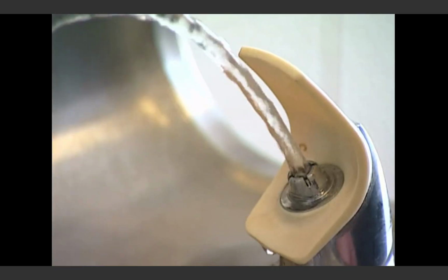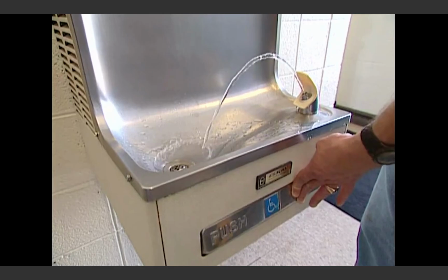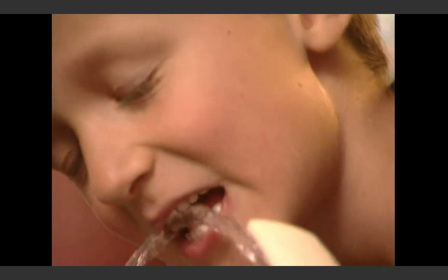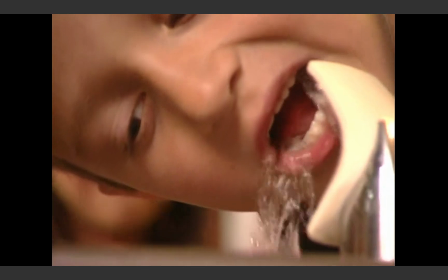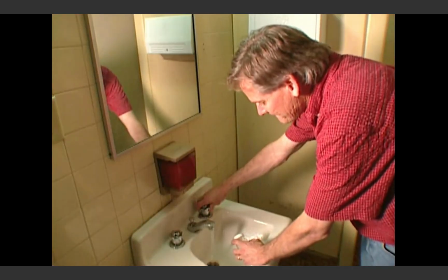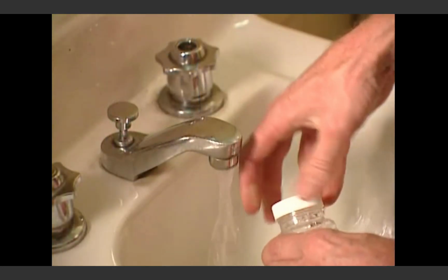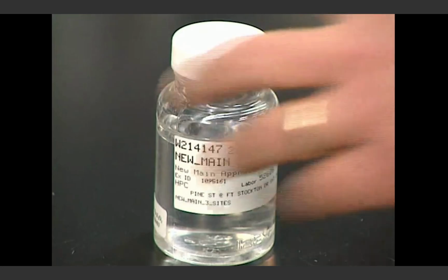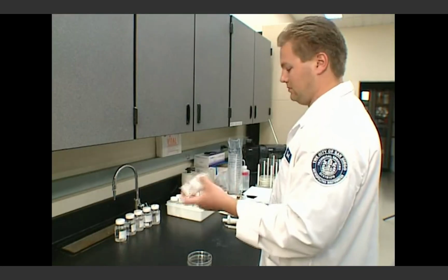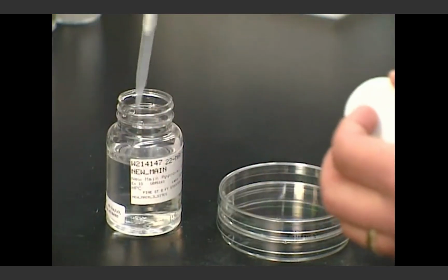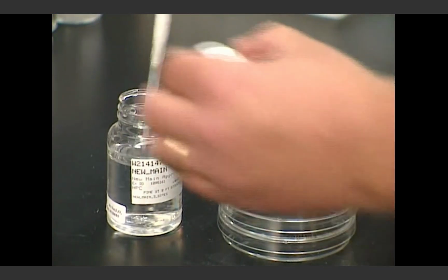The problem was multifold. Poor pressure in the drinking water fountains meant the sample collected represented water that had been fairly stagnant in the pipes. Also, kids had been placing their mouths directly on the faucet. The sinks in the bathrooms and kitchens were suspected of being prone to environmental contamination, such as from water splashing. There was nothing wrong with the drinking water. The samples were simply showing the presence of bacteria at the tap, when in fact the water coming from the distribution system was free of coliform bacteria.